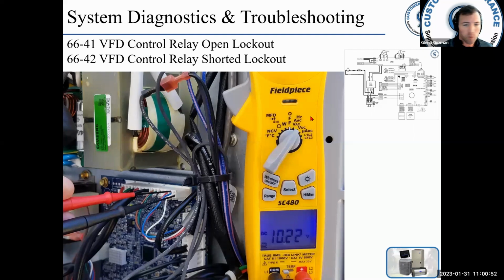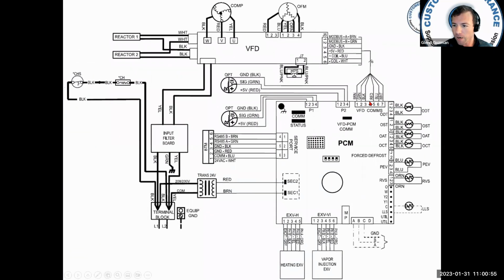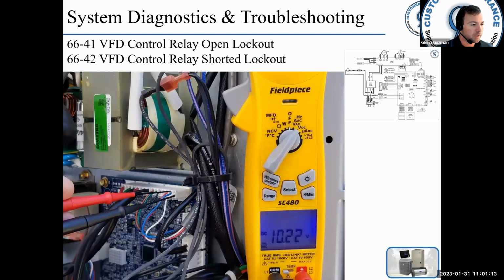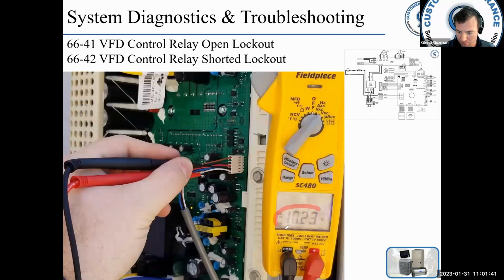So going over to our diagram. All right, so here's the blue and white, pins 6 and 7. Okay, blue and white, that should be my 12 volts DC. I should have 12 volts DC up here, blue and white. All right. To troubleshoot this, remove the PCM VFD harness from the PCM while leaving the other end connected to the VFD. You can ohm this VFD control relay. Okay, so what I would do is pull this plug, okay, and then go to the VFD and ohm that plug. Here's a picture you can see where I'm measuring voltage.